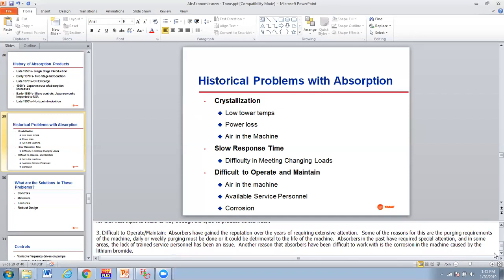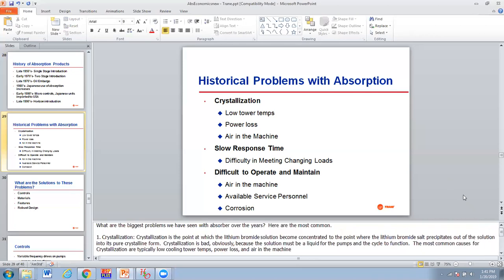Some reasons for this were that purging requirements were manual and had to be done daily or weekly. The lack of trained service personnel was an issue, and so in general they've not had a great reputation over the past 40, 50 years. Corrosion is another problem we've talked about a little bit with lithium bromide. The salt is very corrosive to standard metals.